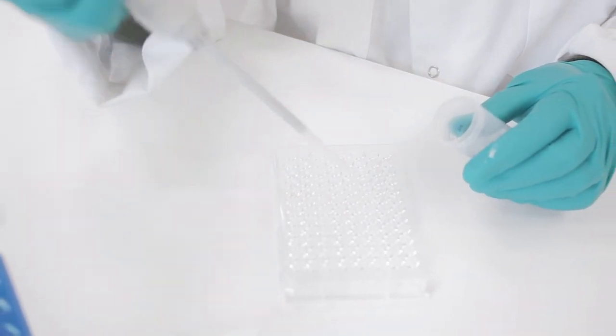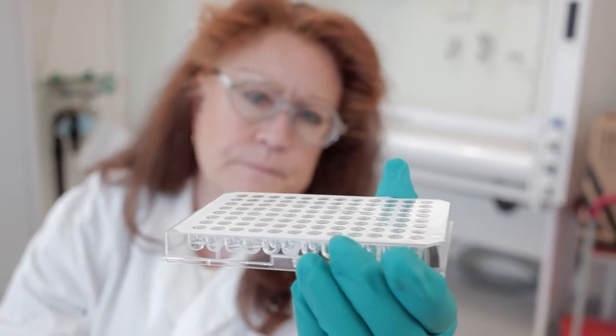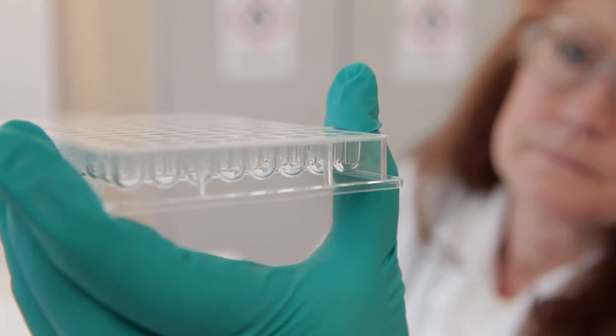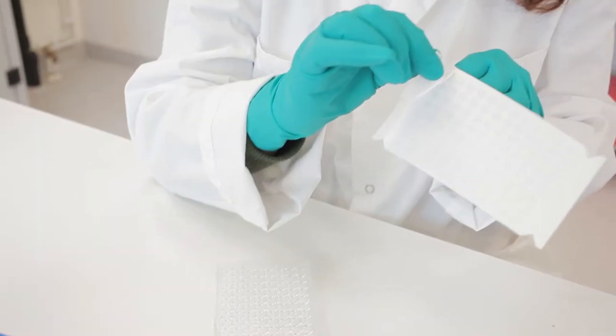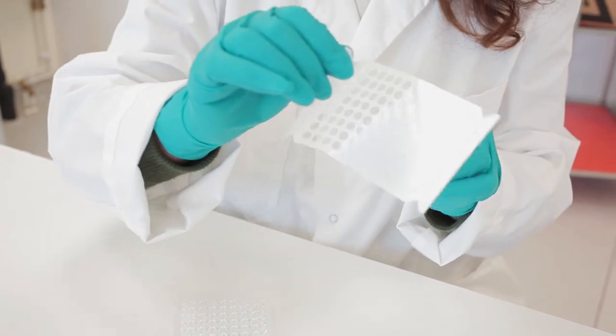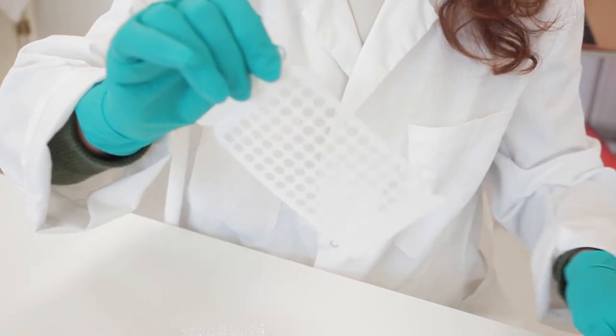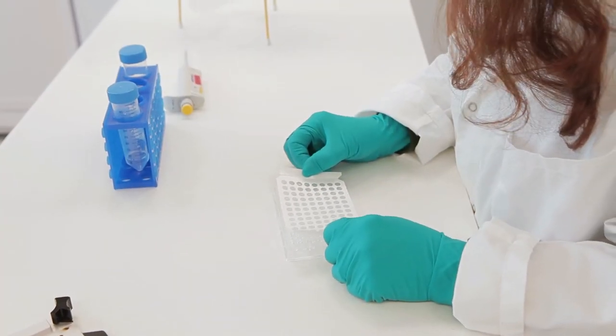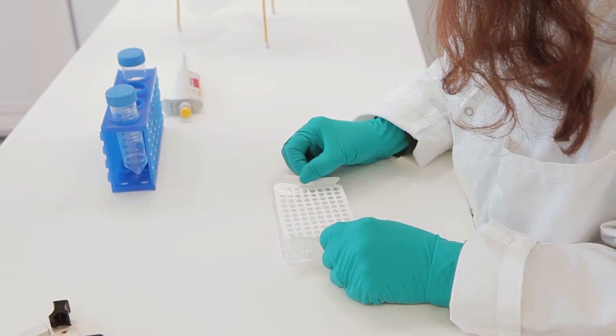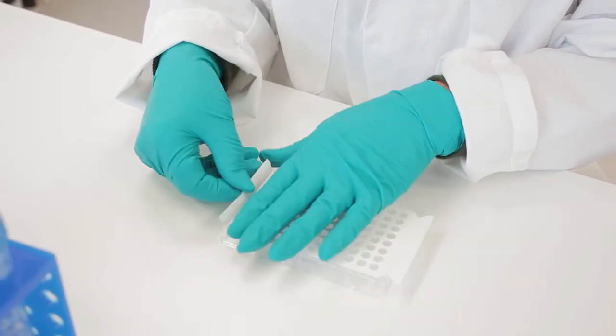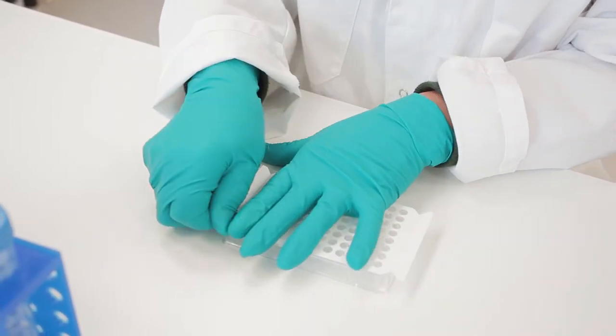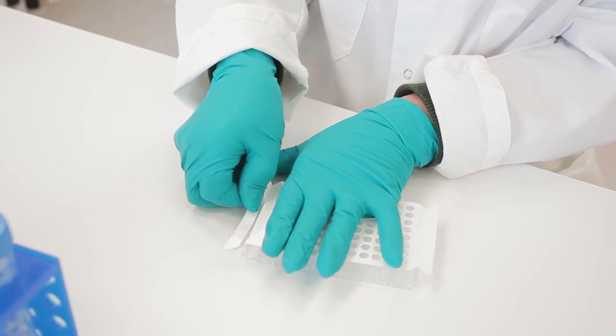When samples are loaded into microtiter plates, check that there are no air bubbles. Cover the plate with the correct adhesive foil. Ensure it is well attached and then remove the tabs at each side by tearing across the perforated edge.